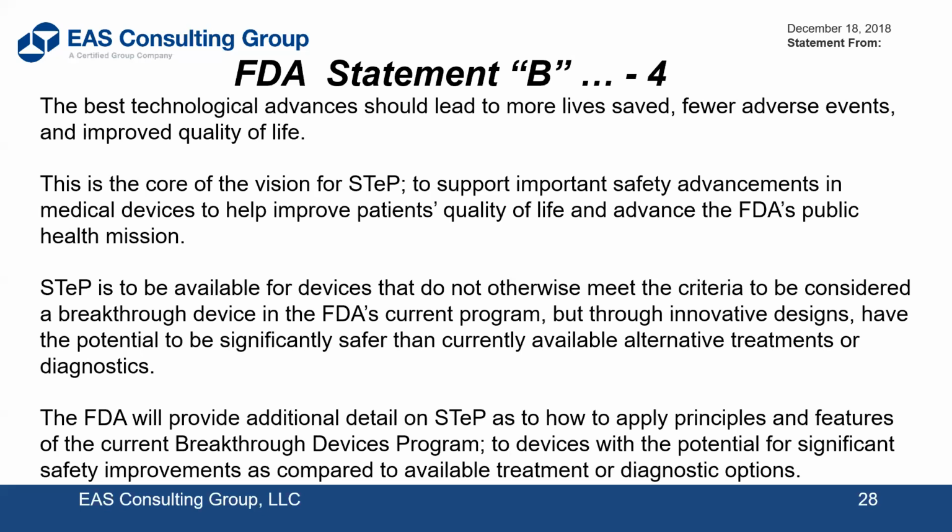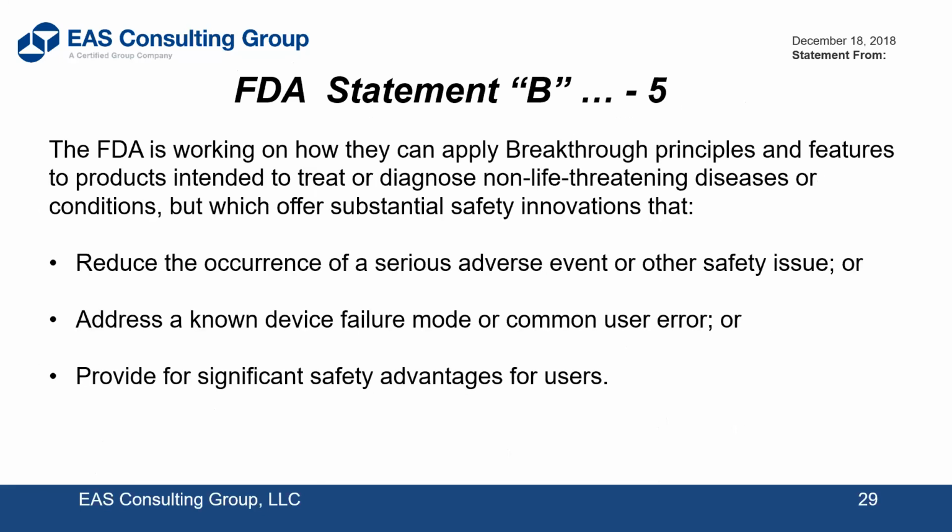But you're reaching out to the agency before you're actually ready to file, when you're in the R&D stage, advanced in the developmental stage. You want to start getting the FDA involved if you plan on taking advantage of breakthrough or STEP, and do it through the Q-Sub. That's what gives them a heads up, so to speak, and then they'll start working with you in a sense like a partner. Now, my experience has not been in STEP or breakthrough, but it has been in one example where the FDA determined that clinicals were required. They did work with us as a partner to explain what they expected.